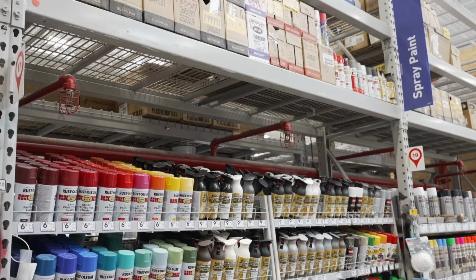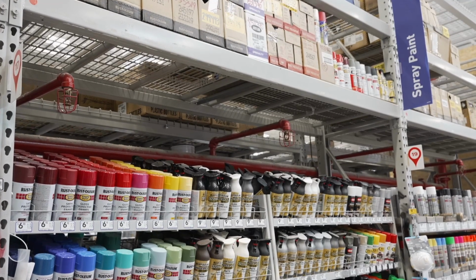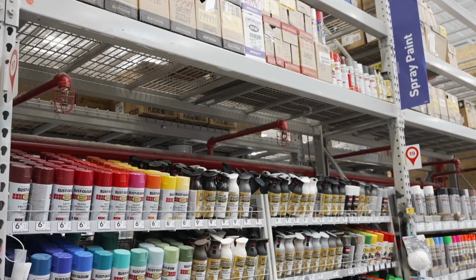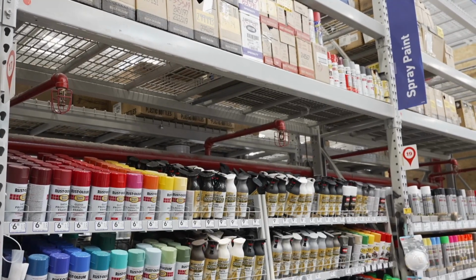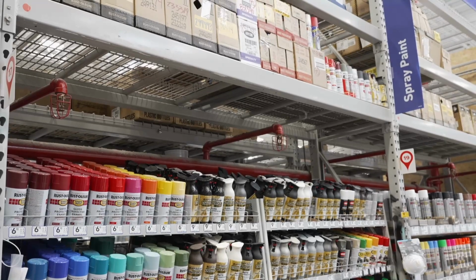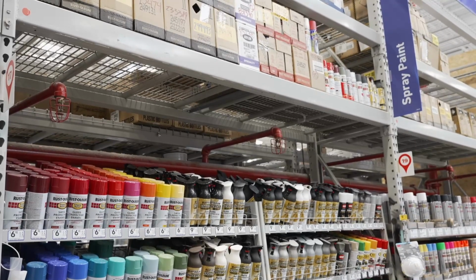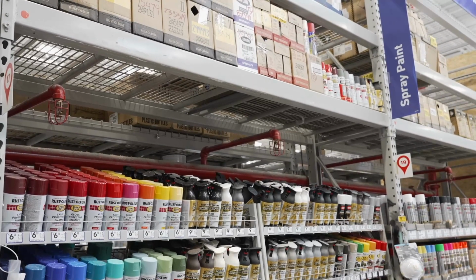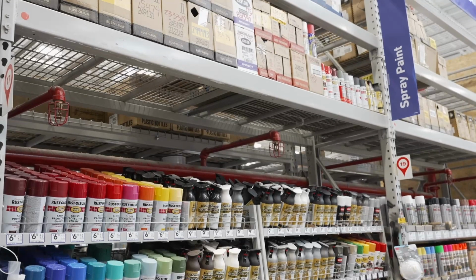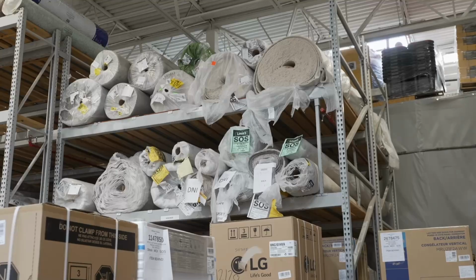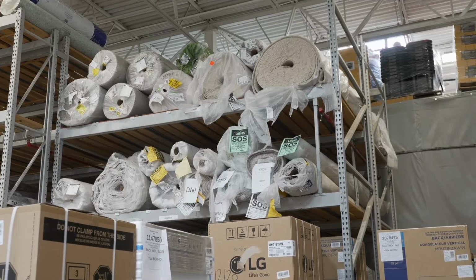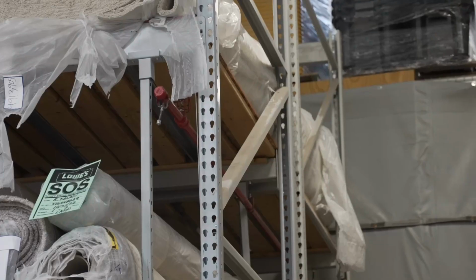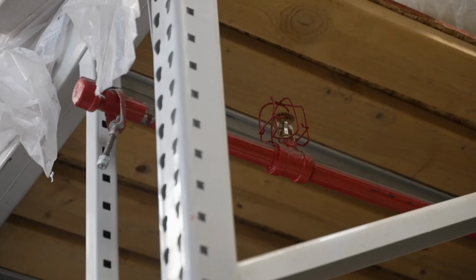Also, for certain high hazard flammables and combustible or flammable gases, they have in-rack protection for that. And it's tighter, no more than 4 feet apart. And you want to make sure those cages are also on. All right, so for the overflow product, they have a back storage rack. This back storage rack is densely packed with carpet. So because of that, it also has extra fire sprinkler protection.